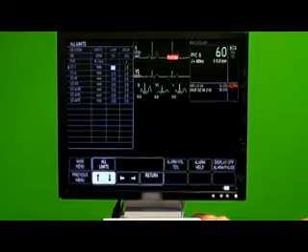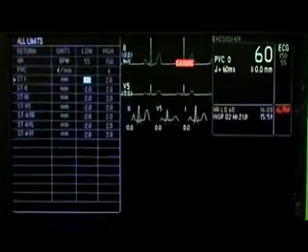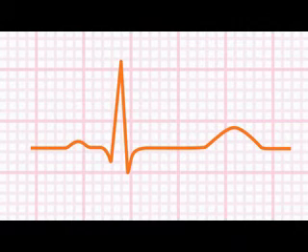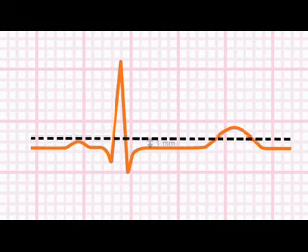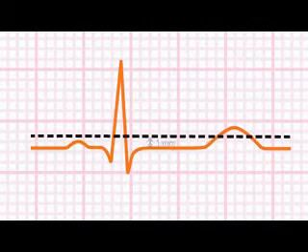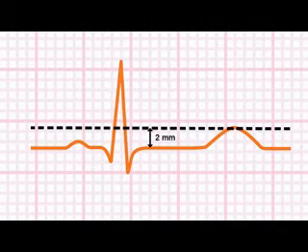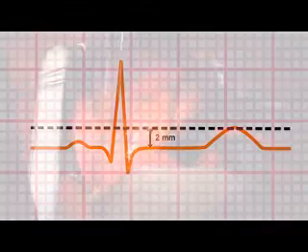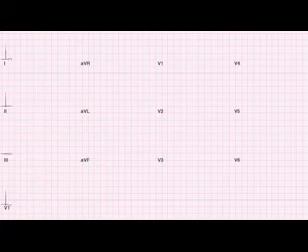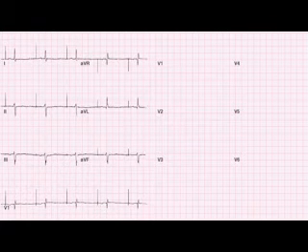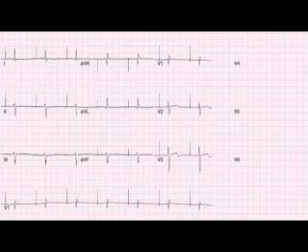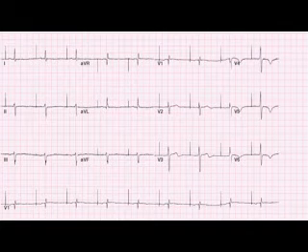ST segment alarms should be set at 1 or 2 millimeters from the patient's baseline, rather than the isoelectric line, to avoid false ST alarms. A setting of 1 millimeter is appropriate for patients at high risk for ischemia, and a setting of 2 millimeters is appropriate for more stable patients. For patients with a pacemaker, you may need to select settings specific to the pacemaker to decrease the possibility of counting pacemaker artifacts as QRS complexes.